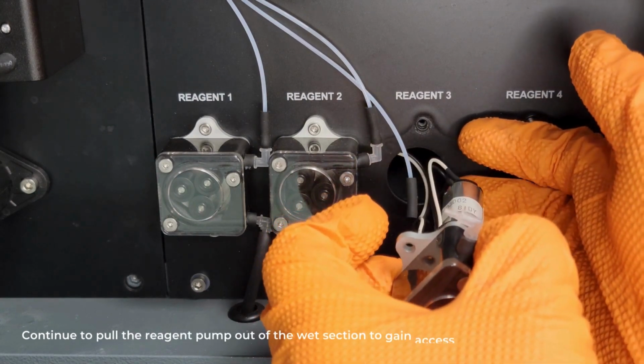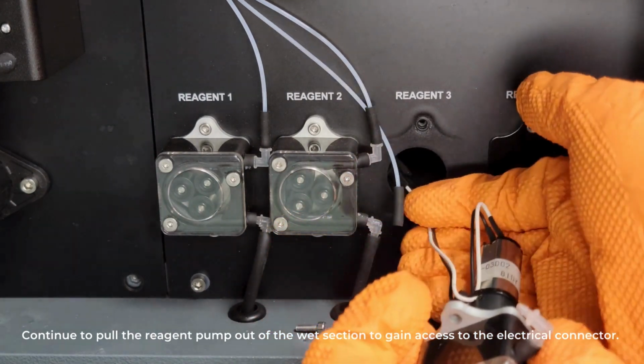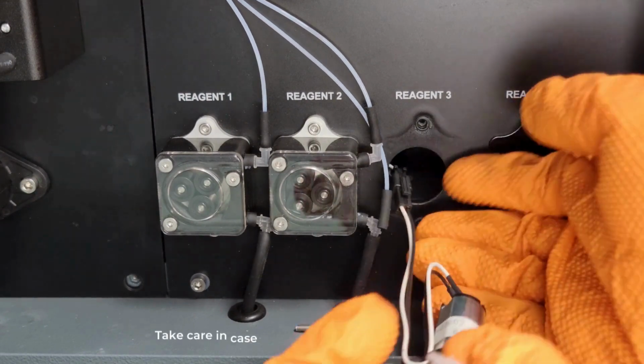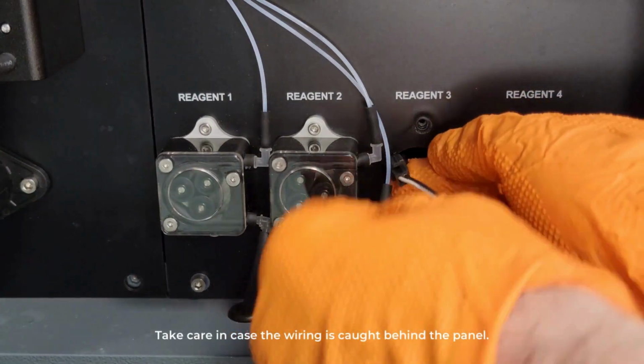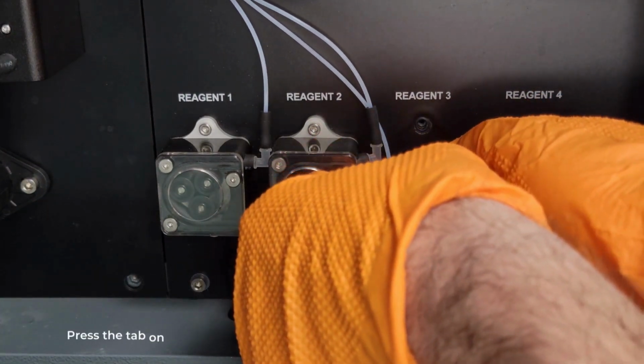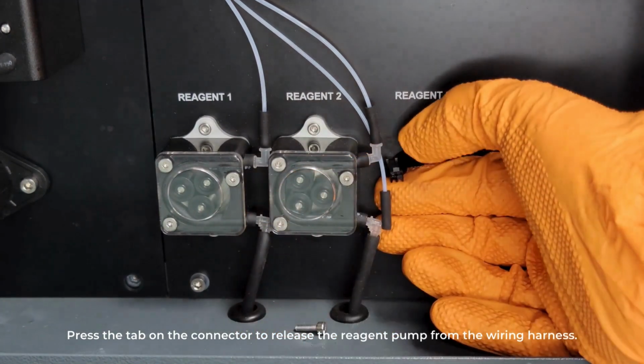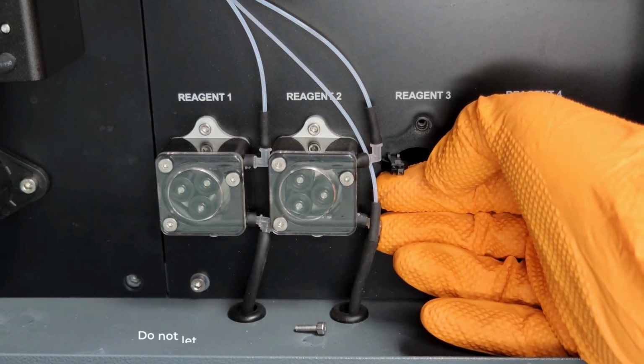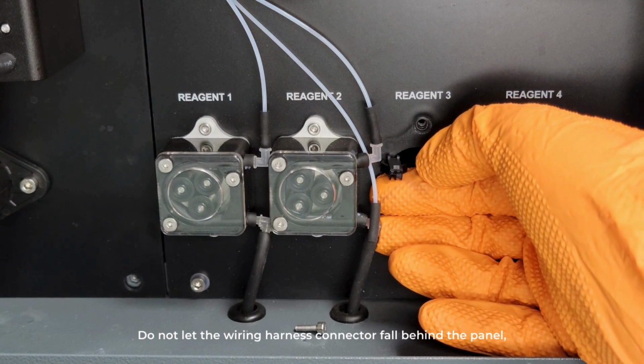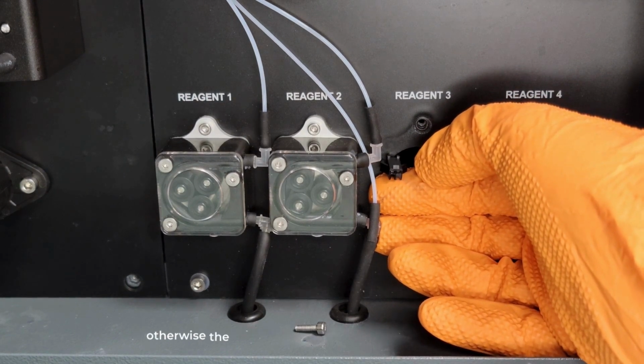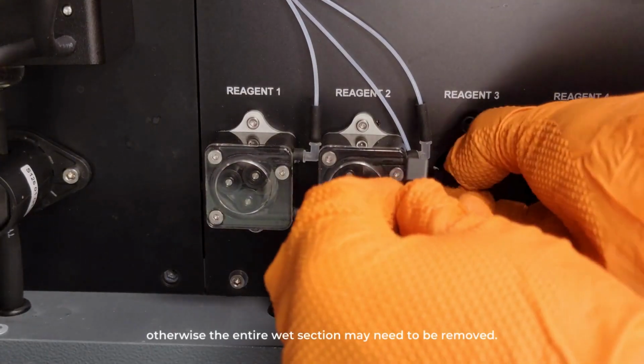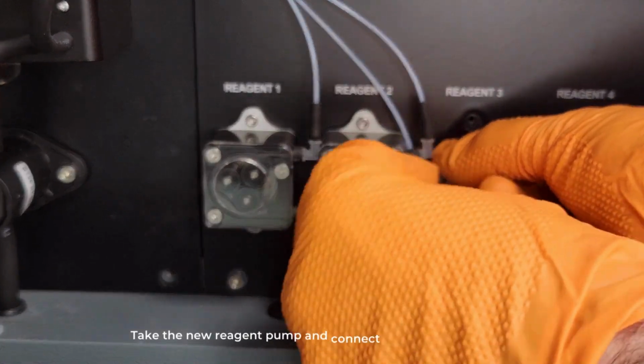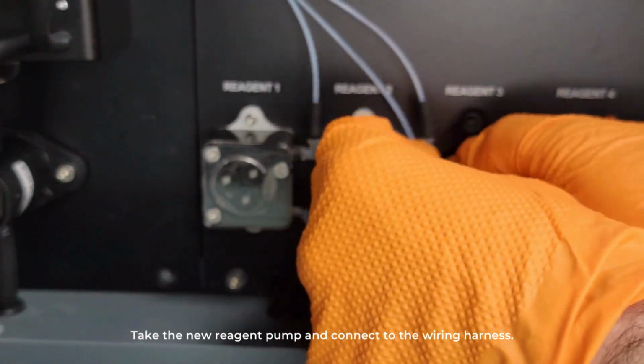Continue to pull the reagent pump out of the wet section to gain access to the electrical connector. Take care in case the wiring is caught behind the panel. Press the tab on the connector to release the reagent pump from the wiring harness. Do not let the wiring harness connector fall behind the panel, otherwise the entire wet section may need to be removed. Take the new reagent pump and connect to the wiring harness.